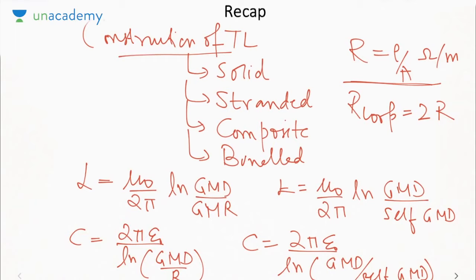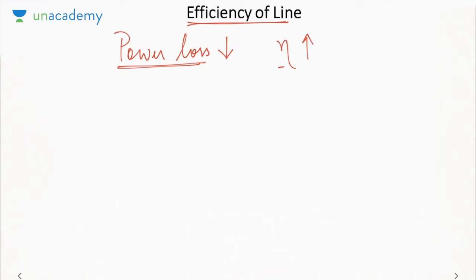On what parameters is the performance judged? So the first parameter that we consider is the efficiency. As I told you, the desirable characteristic of the line is that power loss in a line should be low, so that maximum power reaches from the sending end to the receiving end. So if the power loss is low, that means the efficiency should be high. So how do we define efficiency? It is output power by input power into 100%.